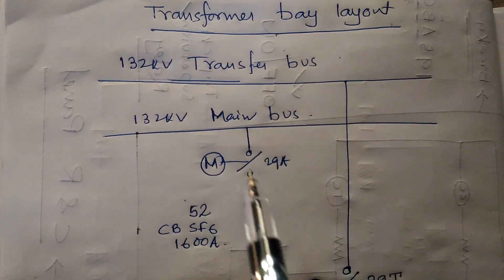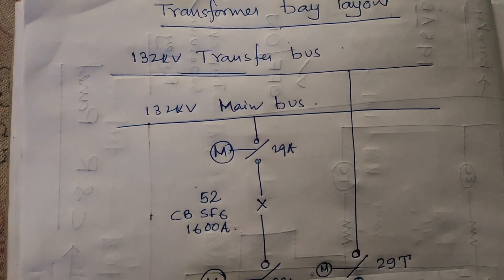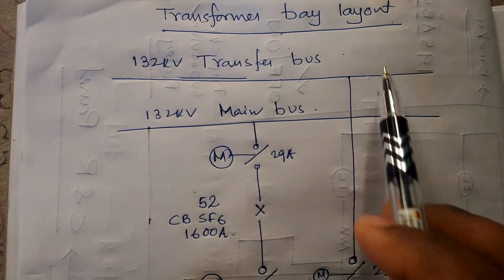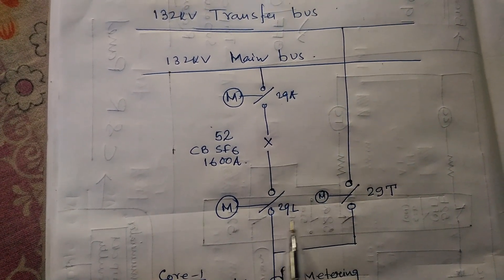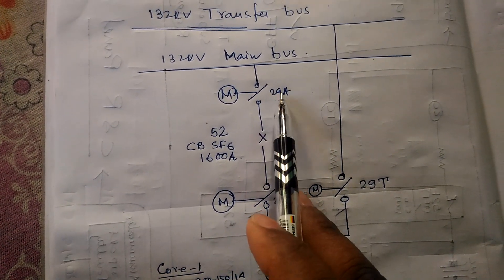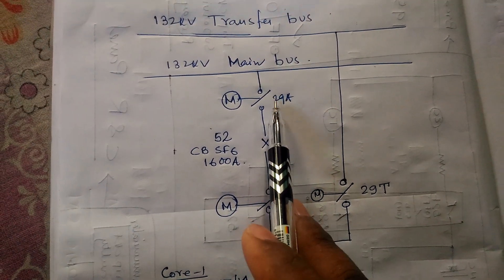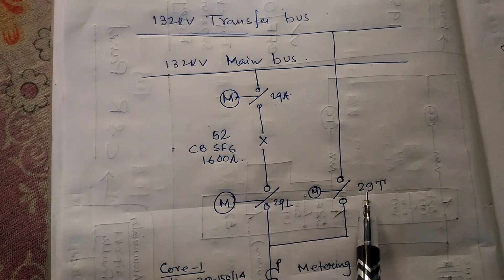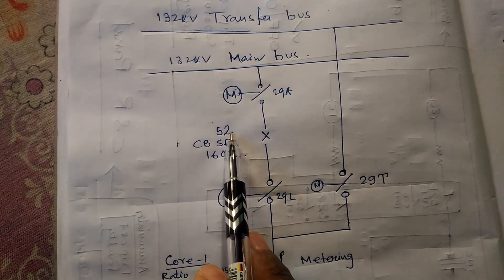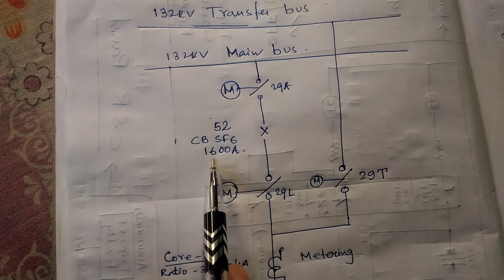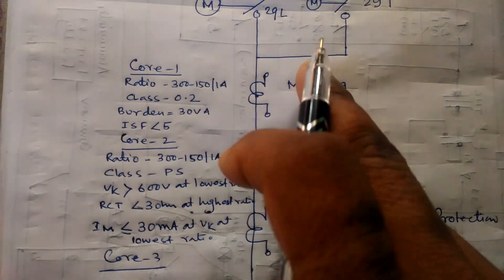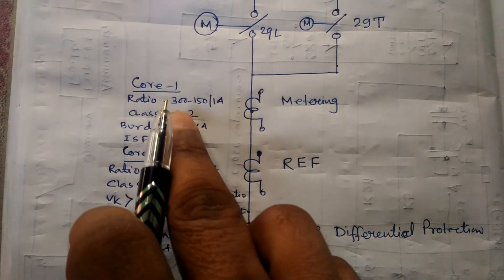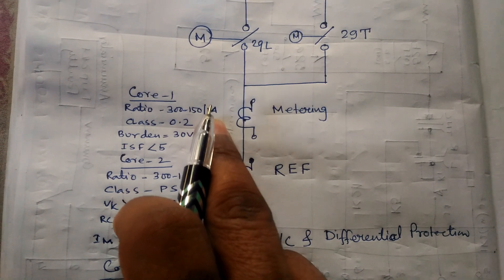The substation has two bus systems: the transfer bus system and the main bus system. Here we have isolators 29A, 29L, and 29T — the main bus isolator, the line side isolator, and the transfer bus side isolator. 52 is the SF6 circuit breaker rated 1600 ampere, 132 kV.